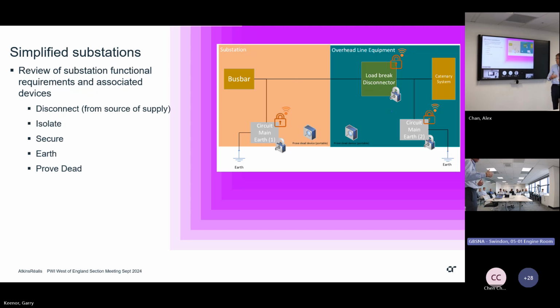So we looked at the basics of the Electricity at Work Regulations. What are the functions of taking an isolation? You've got to disconnect from the source of the supply, and the isolator can be a different function - they can be combined with that disconnection function. You've got to be able to secure that isolation, so you can't have someone come along and just close the switch again and re-energize it.